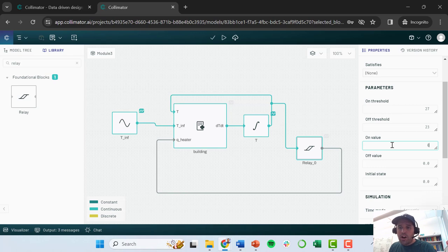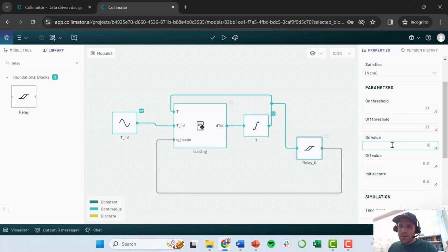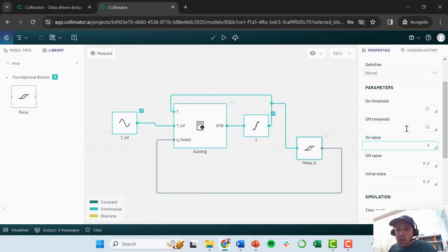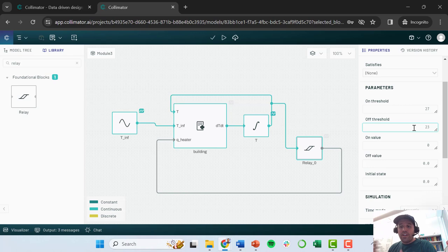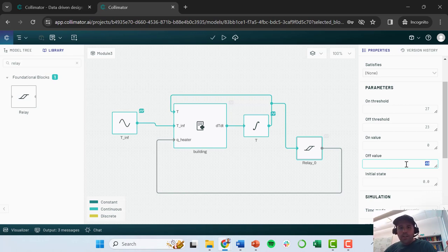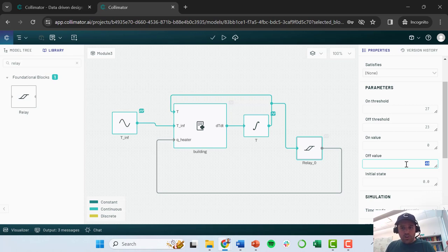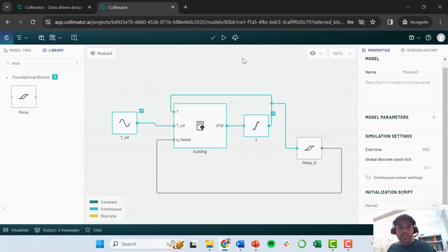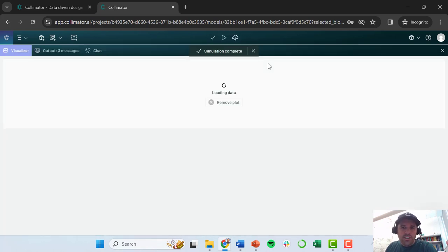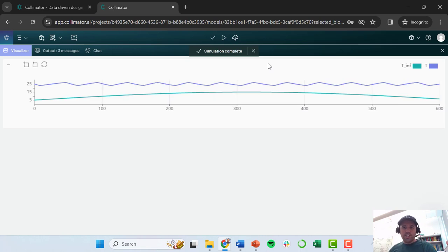And it's turning off. I know that's counterintuitive. But this is the way that this relay block is set up in collimator. Then when we turn our heater off. We're going to expect our building temperature to go back down. And it's going to go all the way down until it hits 23 degrees or our lower limit. And that's when we're going to want the heater to kick on again. So when it hits this lower threshold. We're going to want our heater to kick on again. And be heating to a value of 40. So this should give us. It will not give us perfect temperature control. But it will cause our heater to be switching on and off a lot less frequently. So let's go ahead and run this. And see what happens if we get results that are more realistic.